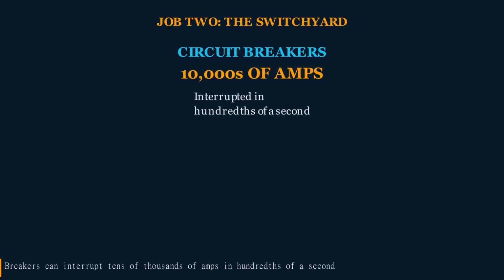Connected to that bus bar are the circuit breakers. These are the heroes of the yard. When a fault happens, a tree falls across a line, lightning strikes, a squirrel bridges a gap, the current doesn't politely rise. It explodes, sometimes to tens of thousands of amps in a fraction of a second, enough to melt metal and start fires. A circuit breaker is a switch built to interrupt that, to force open a connection carrying that monstrous current and snuff out the arc that tries to follow.